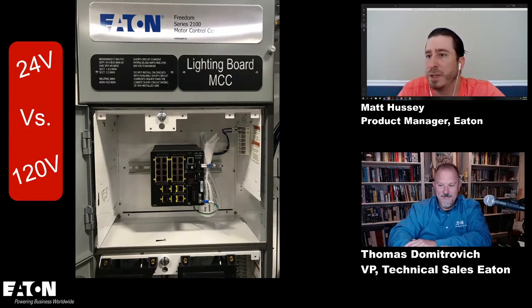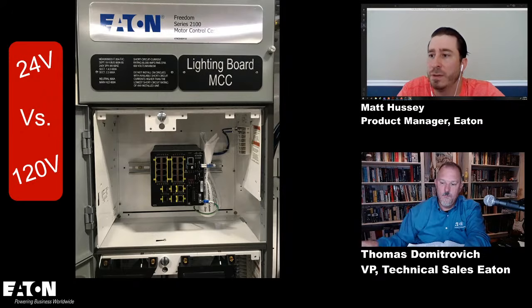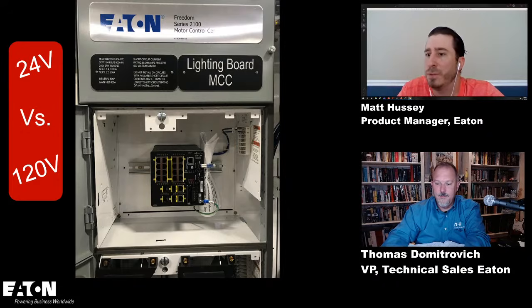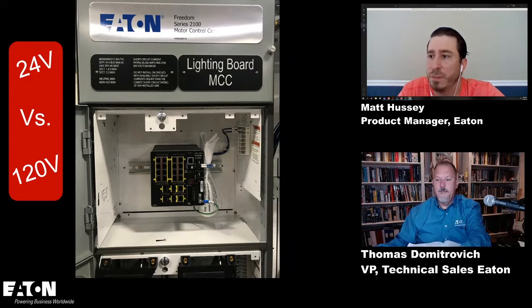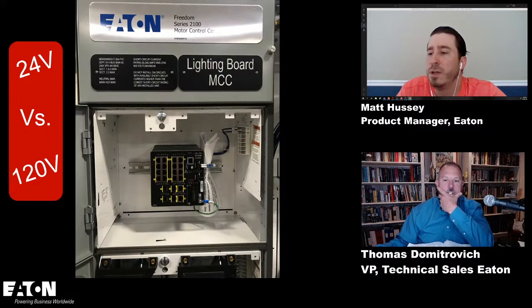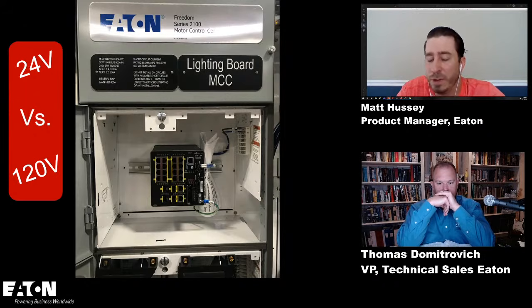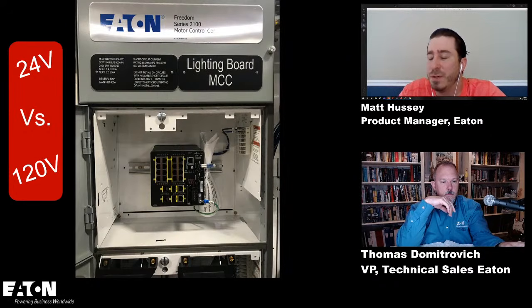So you might have an interposing relay utilized for low power or 24 volts. But then contactor coils will usually still be applied at 120 volts, really just trying to offset anything from bad power. Gotcha. But as equipment goes on, especially with the networking capabilities, there's a lot more capability for providing power reliably to those things. So you'll commonly see something like we're seeing here, where the Ethernet switch is powered off at 24 volts, and as you mentioned, to reduce any of the shock potential, that power is coming from elsewhere, but that's all that's in this unit. You don't see any other 480 volt supply or 120 volt supply. Okay. No shock hazard at all when you open that door.